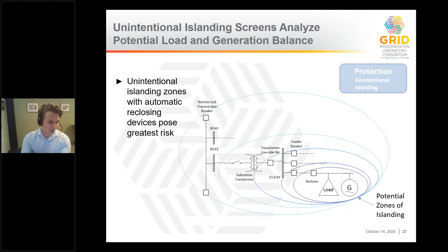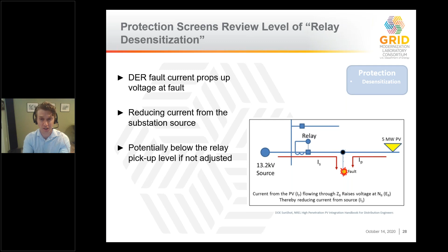There's a concept of relays being desensitized—the inability of the utility's relay to detect an issue on the system. When DER feeds a fault, such as when a tree falls on the line and both the utility system and the DER are feeding that fault, this can lead to the desensitization phenomenon. For safety and reliability, it's important that utility relays can detect faults on the system and quickly isolate the problem. If DER prevents that ability, that's an issue, and it's something hosting capacity screens for.